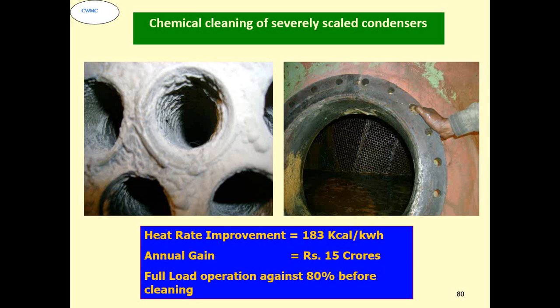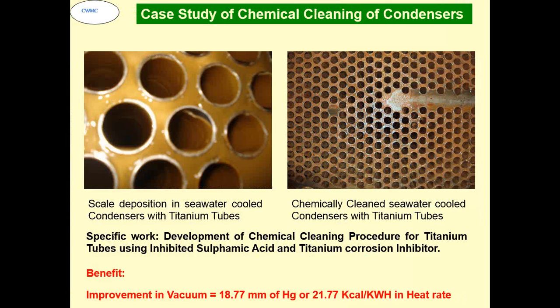But chemical cleaning is just like an antibiotic. It is not the solution. The solution is you must have a proper water treatment so that this problem does not occur. Chemical cleaning is only an antibiotic type of thing. When you have come to that level where there is nothing left, then you do the chemical cleaning. Typically in a seawater system, it also got scaled because of certain operational problems. So there again chemical cleaning had to be resorted to, and we had a good amount of gain.